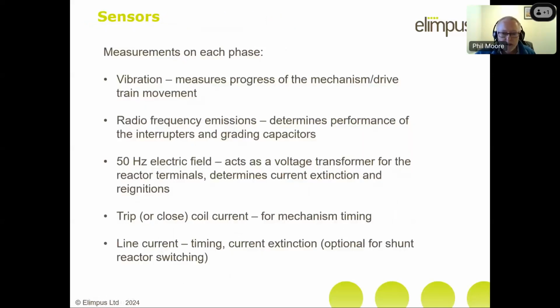So I think I've probably talked about this. The vibration tells you about the mech. The radio frequency emissions give you an idea of what's going on with the interrupters and grading capacitors. The 50 Hertz electric field basically acts as a voltage transformer for the reactor terminals. No reactors have VTs assigned to them. When you open the circuit breaker, you can't see what the reactor terminal is doing. And that signal is very important because it tells you where the current goes out, where the arc stops, and it also tells you about reignitions.